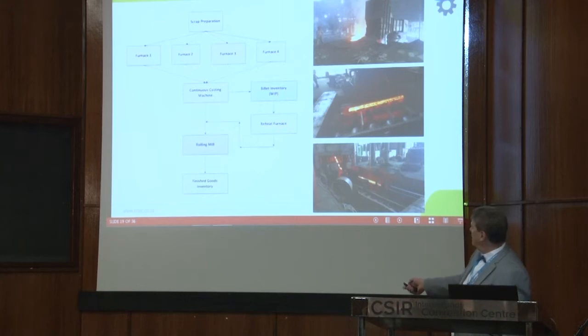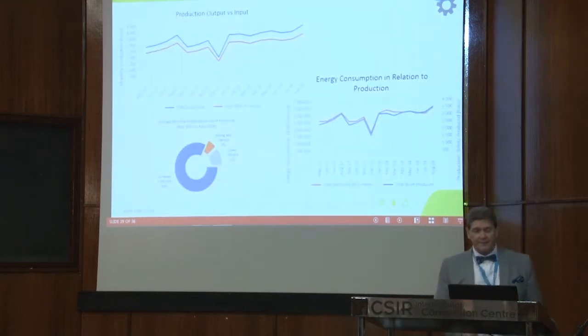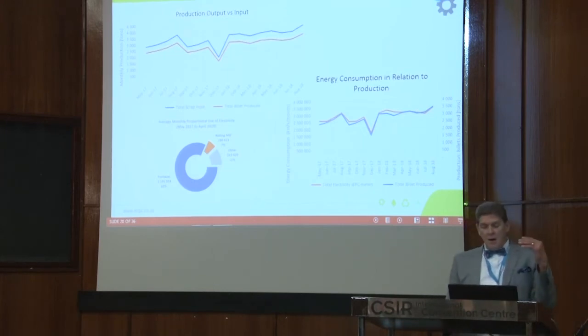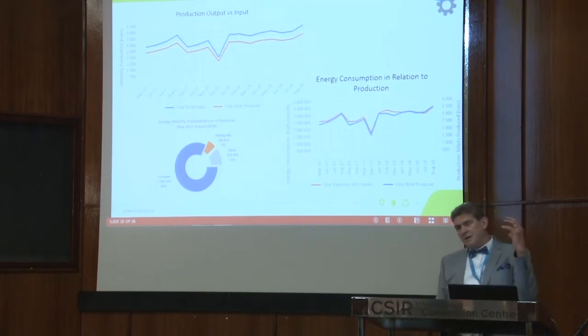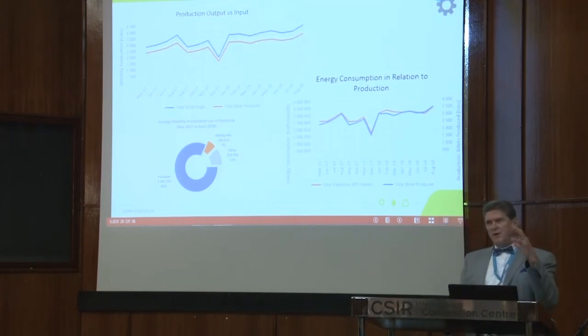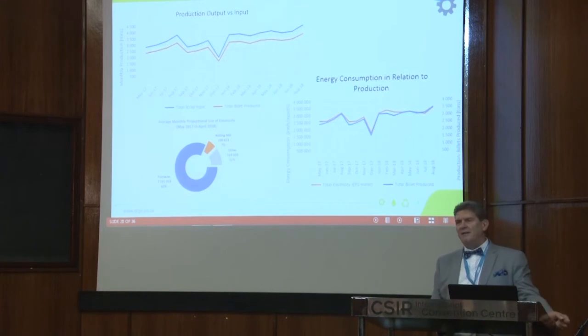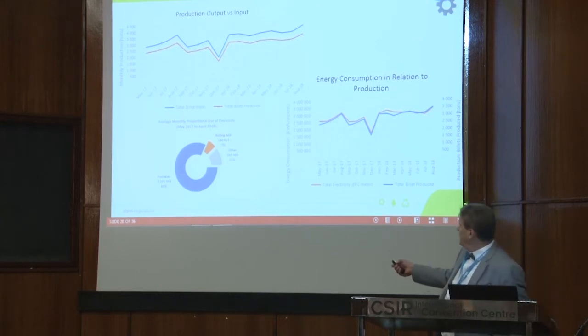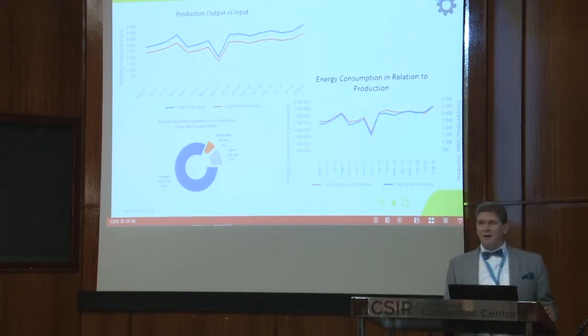When we started to analyse it, the first graph — production versus output — showed scrap coming in versus what goes out. Recall I said melt losses should be around 2% due to oxidation. This plant was showing almost 20%. So there was a huge opportunity: the difference between the blue and yellow trend lines. We then looked at energy consumption in relation to production and could see a clear correlation between electricity consumption and rebar production. That told us we had zeroed in on the driver. In terms of significant energy users, the furnaces were by far the biggest at 82%, with auxiliaries making up the rest.